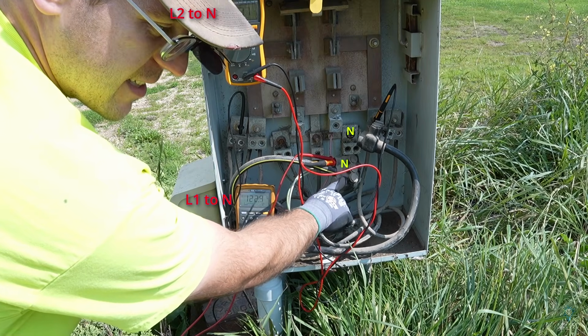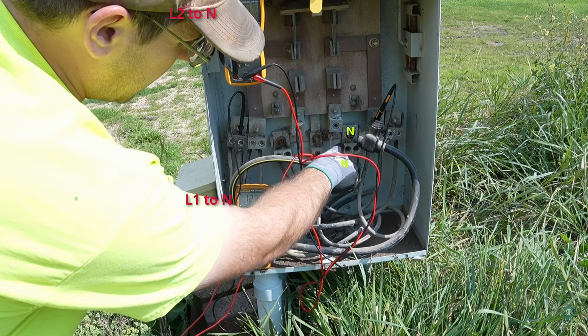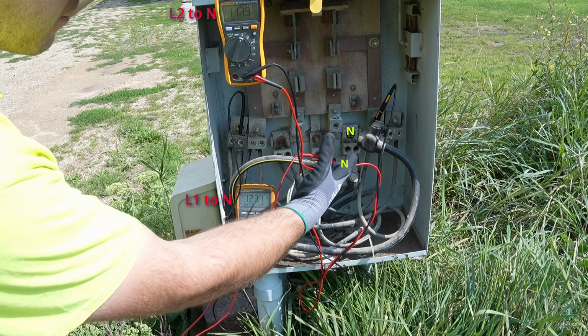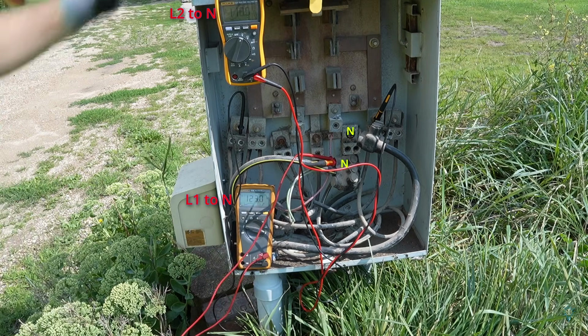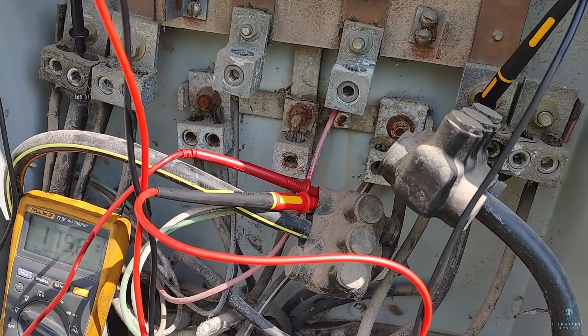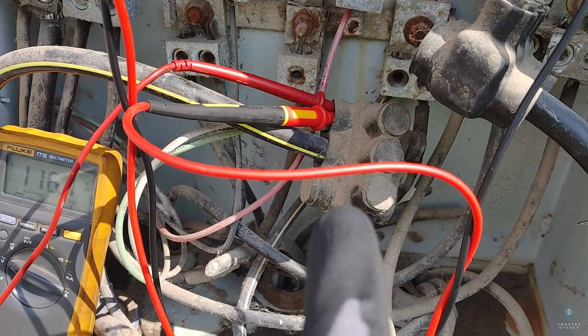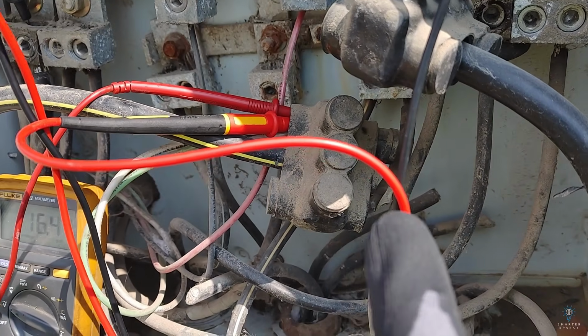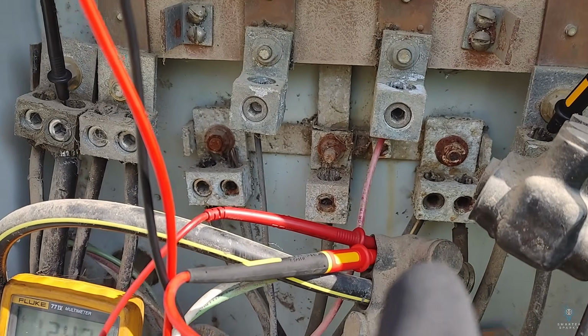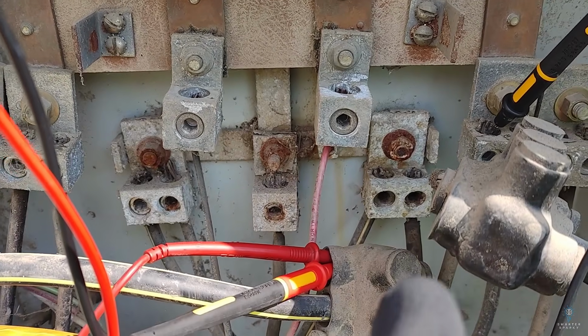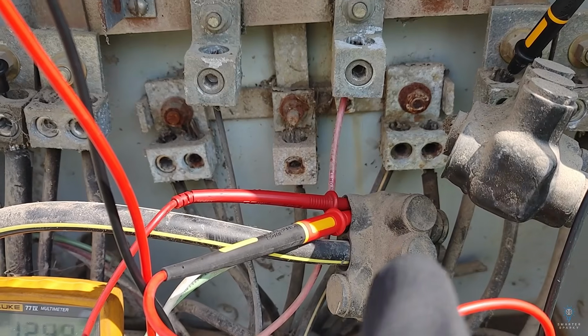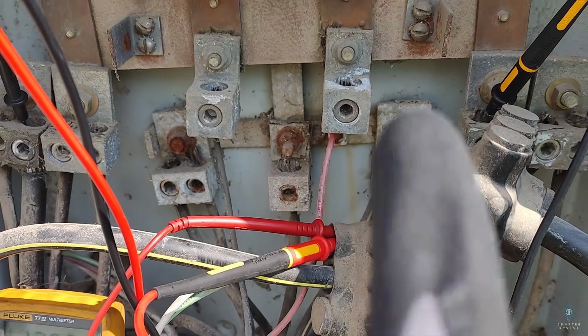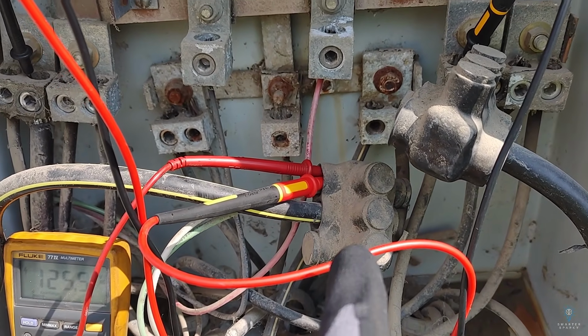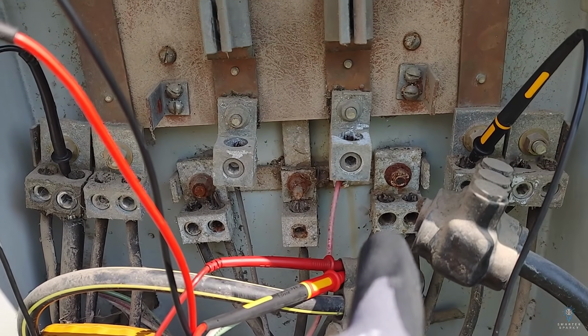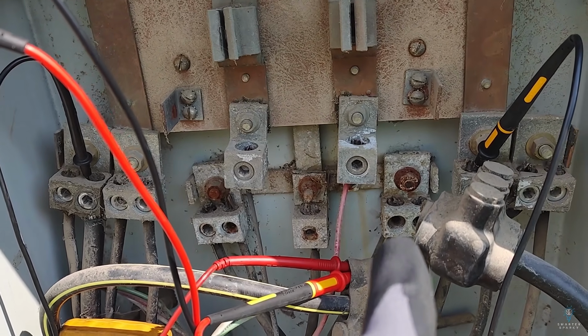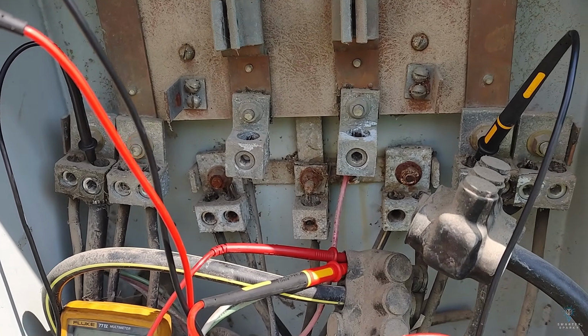So between this connector right here and that lug that is connected to, I'll get the camera in here in just a minute and show a little bit of a close-up. All right, so the way this mess works is this Polaris connector connects to that little piece of wire, which connects to that lug back there. So it's like they did like a little 4-inch jumper, hit that Polaris connector, and I almost guarantee the reason that Polaris connector is there is because they did not want to touch those lugs 15 years ago when they did this. I don't know exactly when they did this service change.